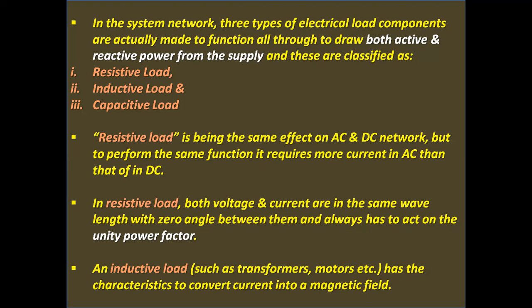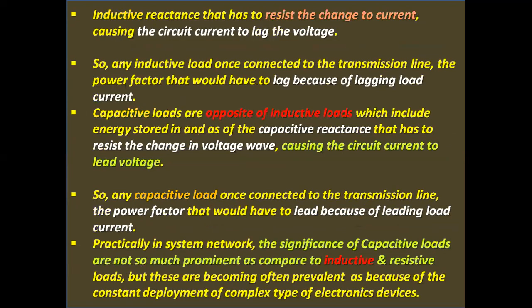And inductive load, such as transformers, motors, etc., has the characteristic of converting current into a magnetic field. Inductive reactance resists the change in current, causing the circuit current to lag the voltage. That's the difference between resistive and inductive. So, any inductive load once connected to the transmission line makes the power factor lag because of the lagging load current.